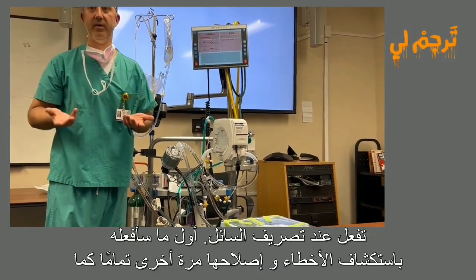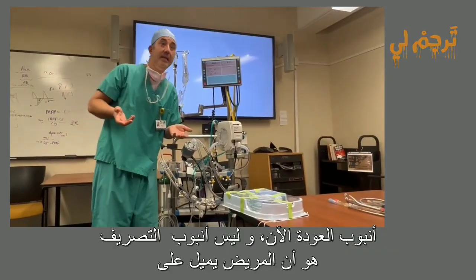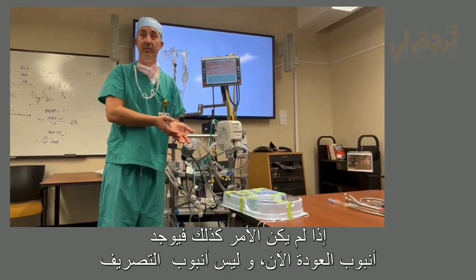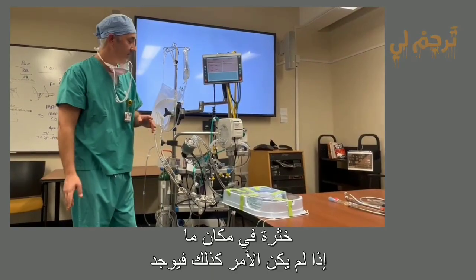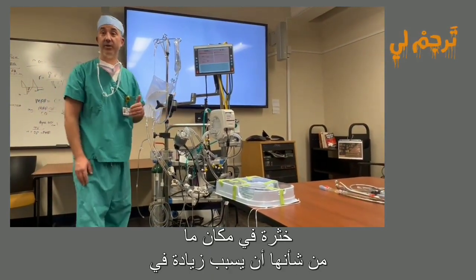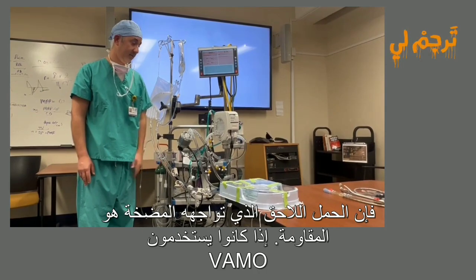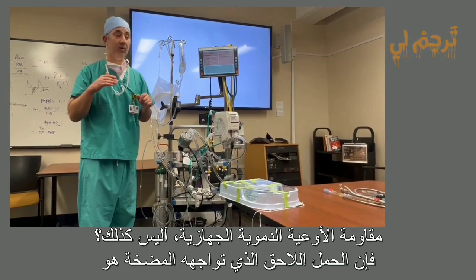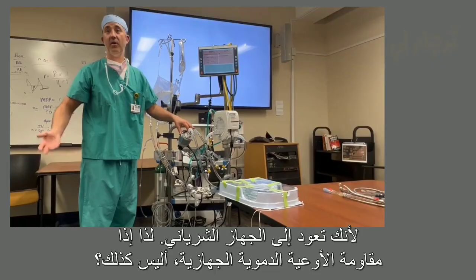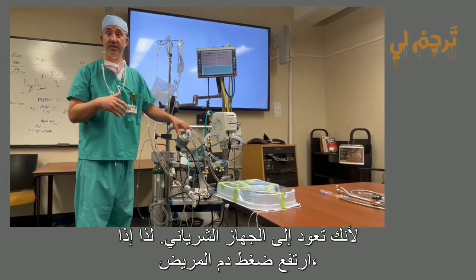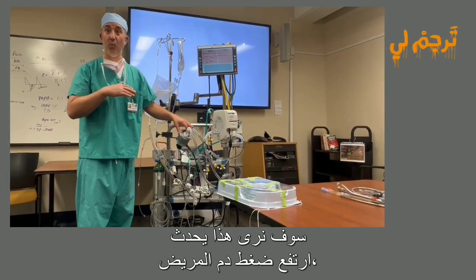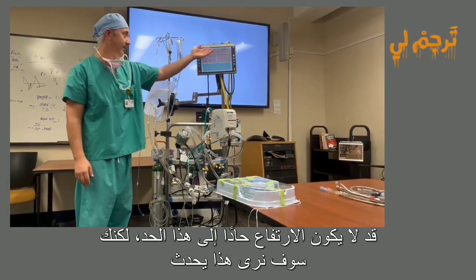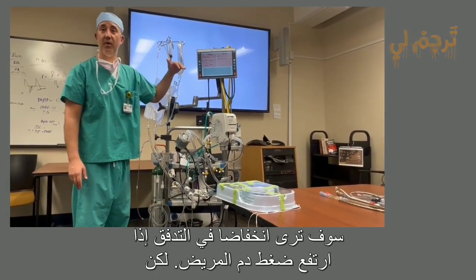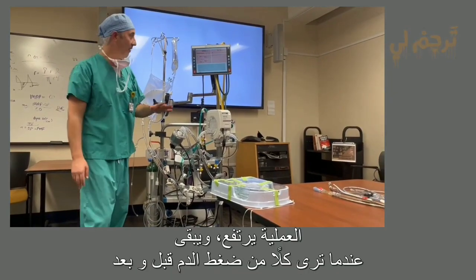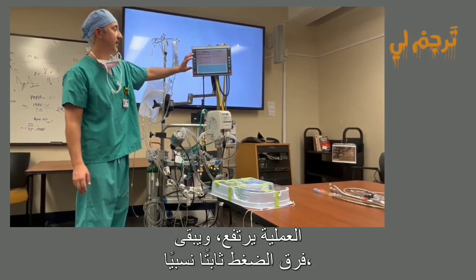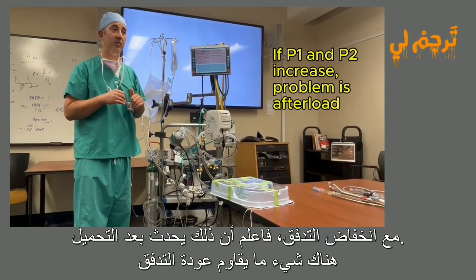So you're going to troubleshoot again, just like you did with drainage. The first thing I would do is check whether the patient is leaning on the return tubing now, not the drainage. If that's not the case, is there clot somewhere after the oxygenator that would cause an increase in resistance? If they're on VA ECMO, the afterload that the pump is facing is SVR, right? Because you're going back into the arterial system. So if the patient's blood pressure went up, you're going to see this happen. It might not be this dramatic, but you would see a drop in flow if the patient's blood pressure went up. But whenever you see both pre and post membrane pressures go up and your delta P stay relatively the same and a lower flow, think afterload.